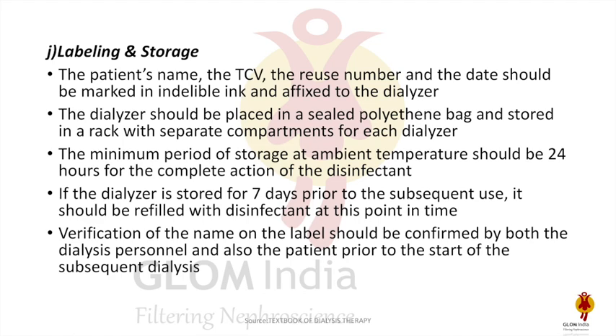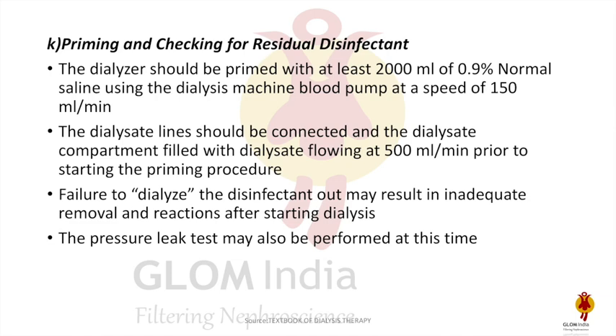Most importantly, verification of the name on the label should be confirmed by both the dialysis staff and the patient prior to the start of subsequent dialysis to prevent errors. For priming, generally 2000 ml of 0.9% normal saline is used with the dialysis machine blood pump at 150 ml per minute. The dialysate compartment should be filled with dialysate flowing at 500 ml per minute prior to starting priming, to clear the dialysate compartment. Failure to clear the disinfectant may lead to inadequate removal and severe reactions.